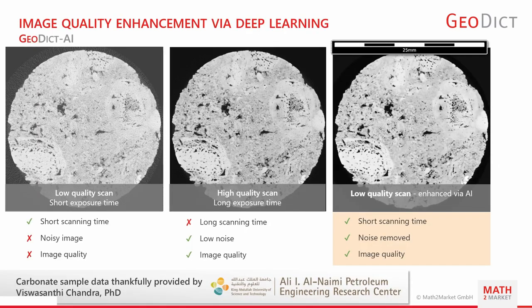The first feature I want to talk about is image quality enhancement via deep learning. When taking samples with a micro CT there's always a compromise. You can either use a short exposure time for each projection, which means higher sample throughput per day but noisy and low contrast images. On the other hand, if you take longer exposures or average many short exposures, you have a long scanning time and low throughput but you get a low noise, high contrast image.